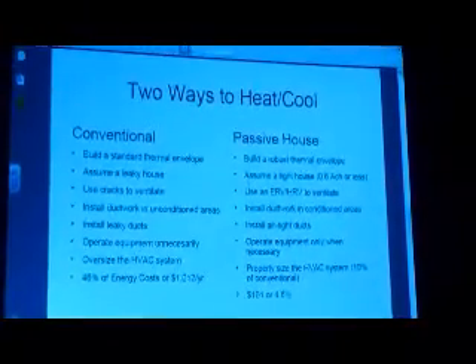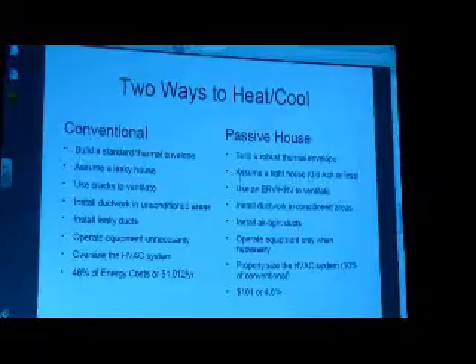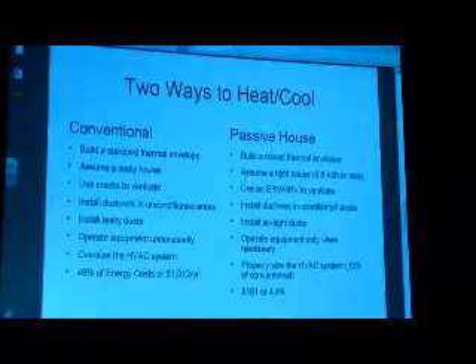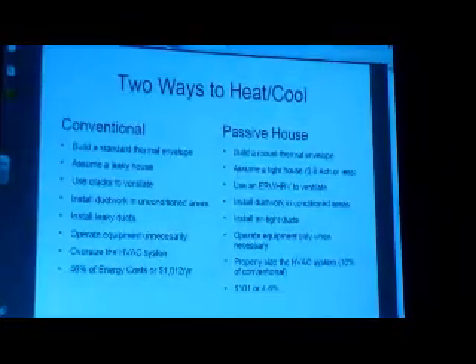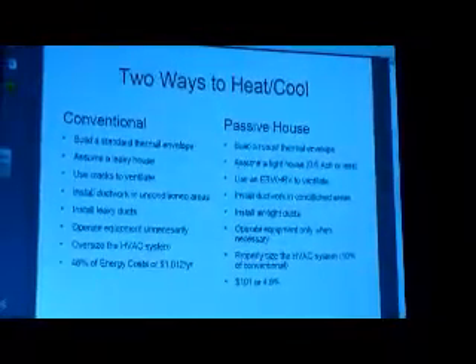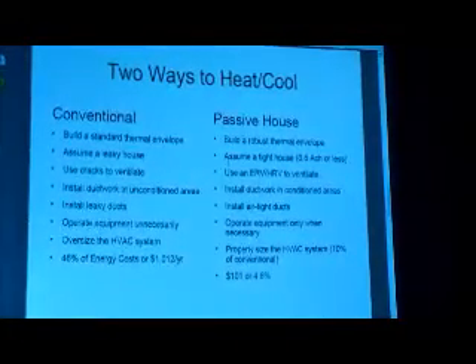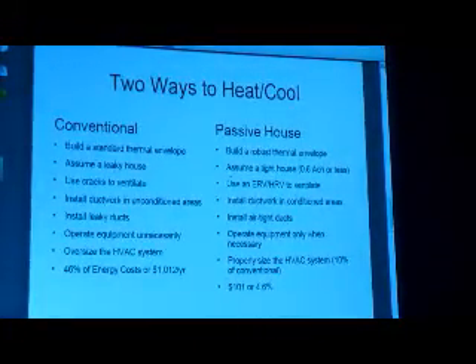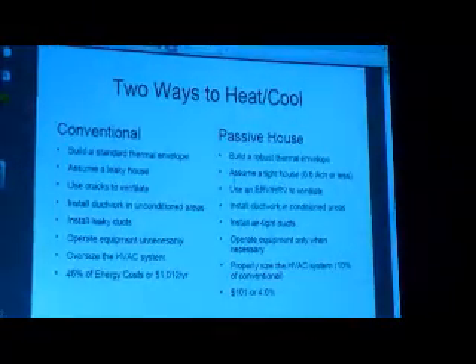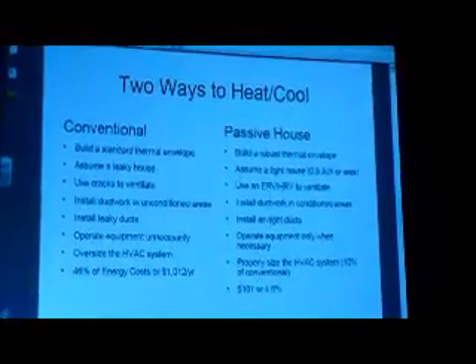Now, on this side, we have Passive House. The assumptions are completely different. You start with a robust thermal envelope: very thick insulation, very high air tightness standards, and you use an ERV to ventilate, so you're no longer breathing through your underwear. Then you install ductwork, all in conditioned areas, so there's no heat loss, and you make it airtight. You operate equipment only when necessary, because there's so little heat loss, only during the very extreme days of the year. And because the load is so tiny, you can properly size your system. You don't need to over-engineer it.